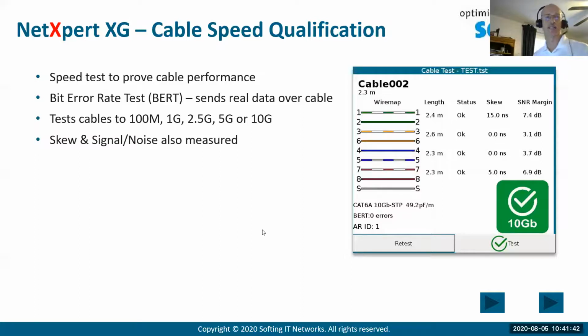So the significance of that test is, often the problems with the cable are at one end or the other — where it's terminated, the connector — and oftentimes the way to get up and running quickly is to re-terminate the cable if there was damage done there. But if the damage is somewhere in the middle of the cable, it doesn't matter how many times the connectors are re-terminated. So that's why it's very good to have a tool like the XG, which has that TDR, time domain reflectometer technology, which is a way to pinpoint where the wiring issues are to save lots of time.